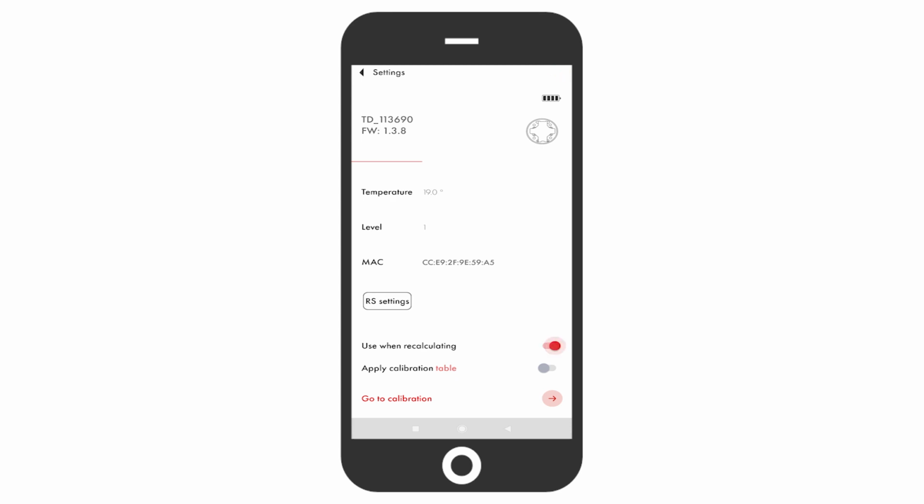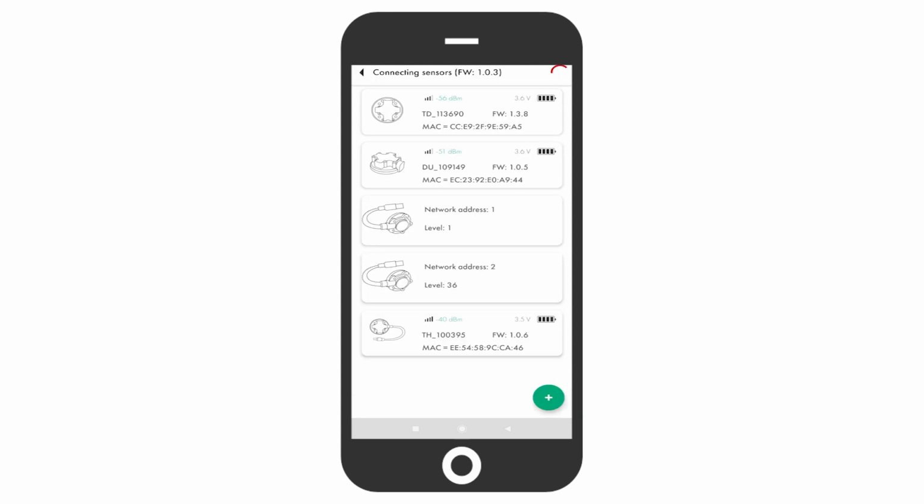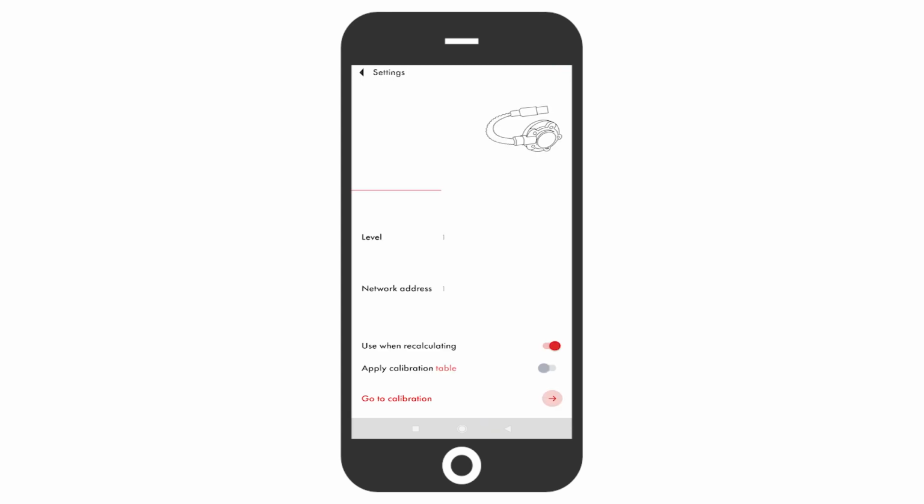However, if there are two pairs of sensors, for example, and you need a total or average value of each pair to be displayed separately, unfortunately, that cannot be done. You can only get a total or average of one pair, and the readings of two other sensors will have to be displayed in two more virtual windows.